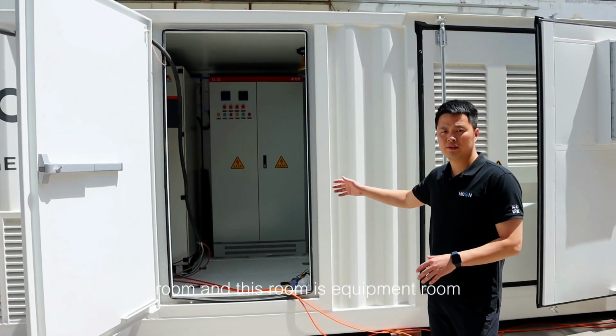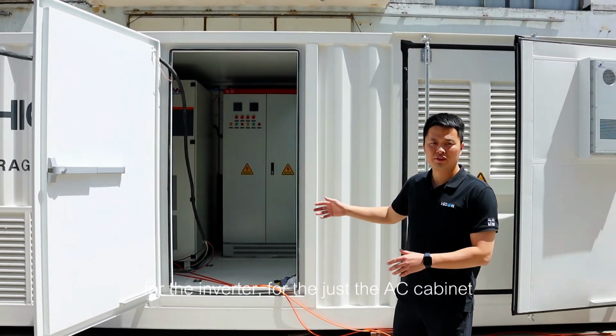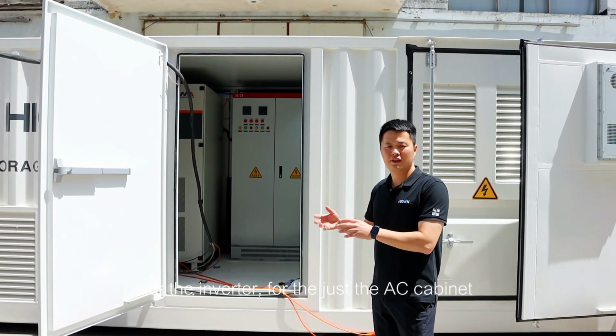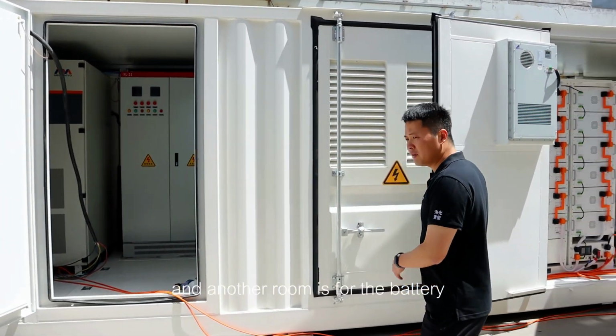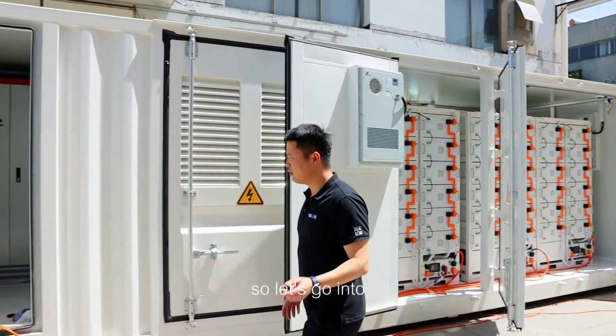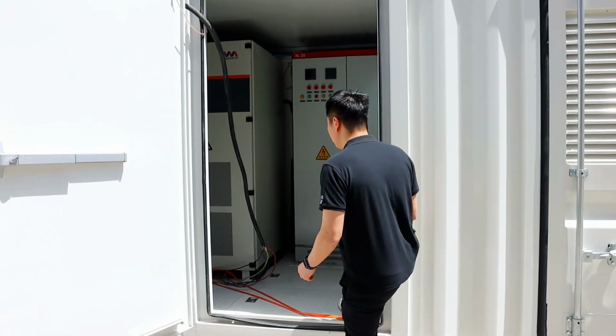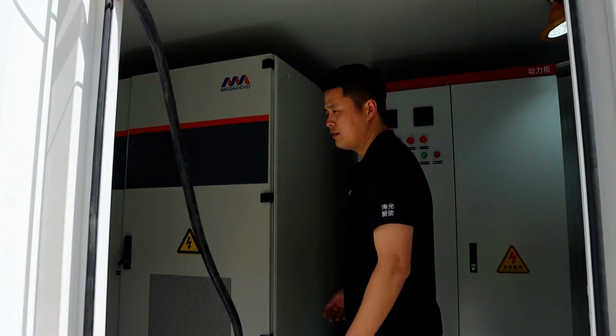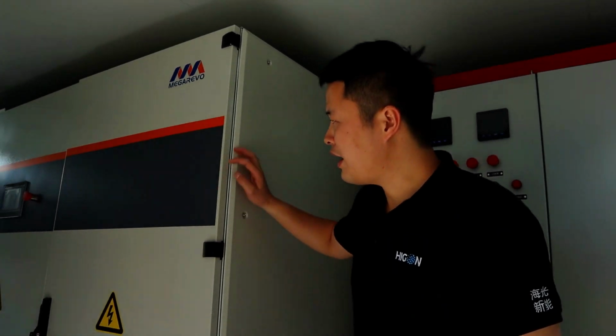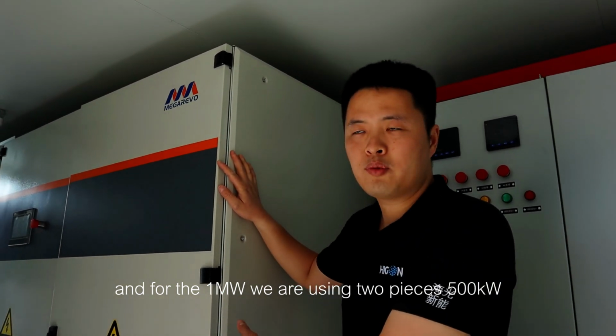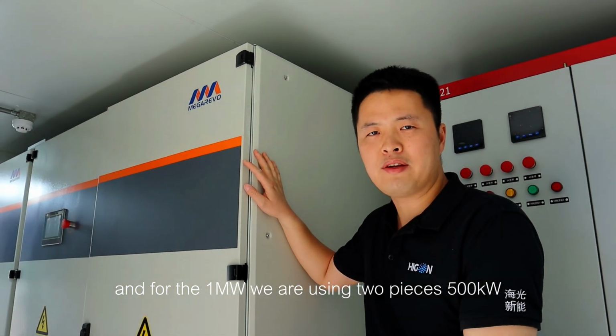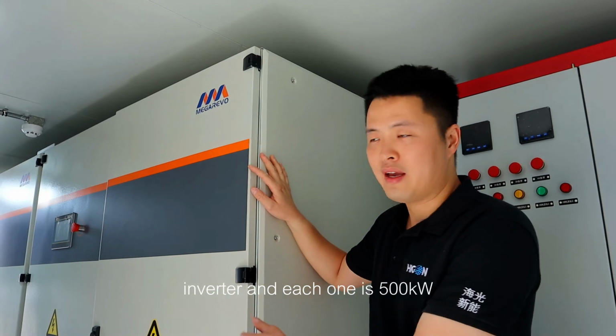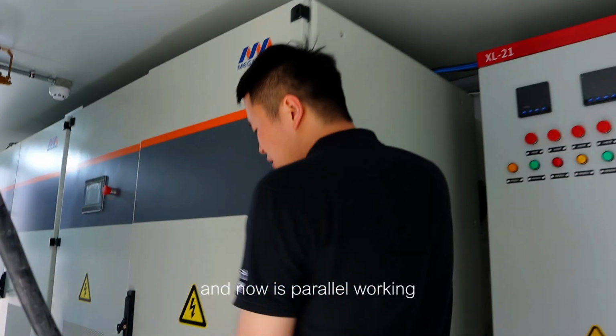This room is the equipment room for the inverter and the AC cabinet, and the other room is for the battery. So let's go in. We can check here: for the 1 megawatt, we are using two 500 kilowatt inverters, each one 500, and now they are working in parallel.